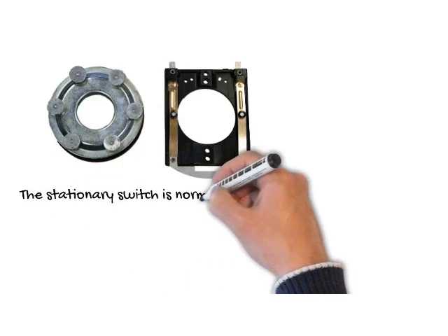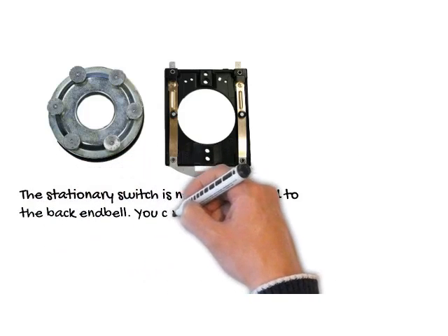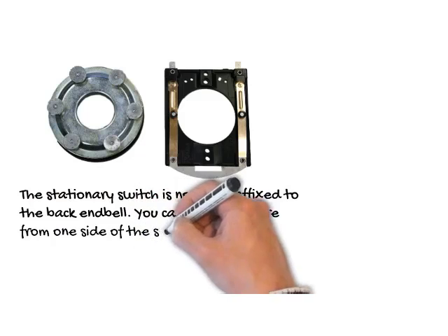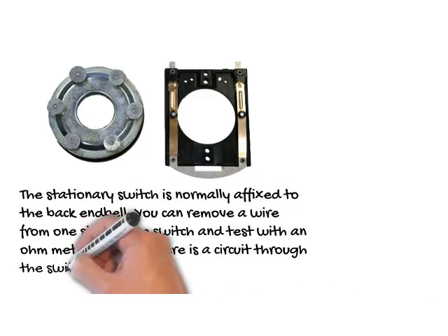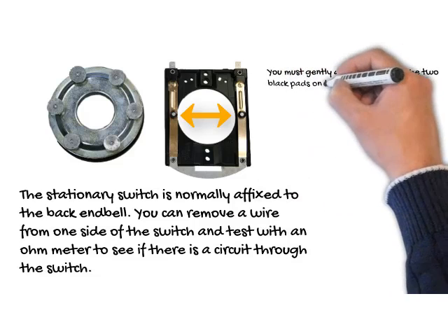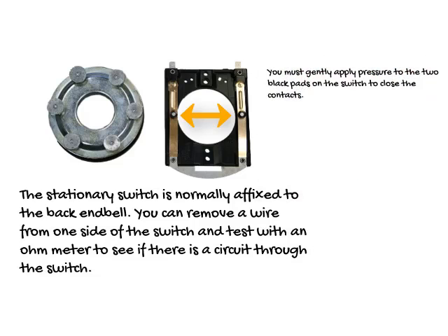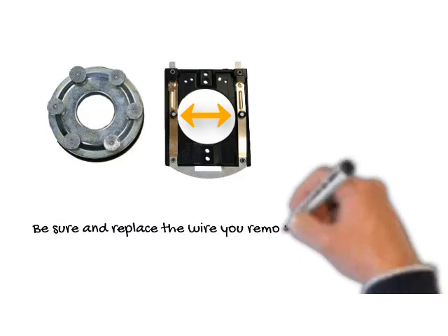The stationary switch is normally affixed to the back end bell. You can remove a wire from one side of the switch and test with an ohmmeter to see if there's a circuit through the switch. You must gently apply pressure to the two black pads on the switch to close the contacts.